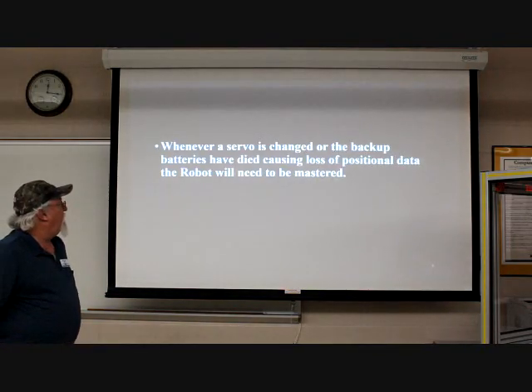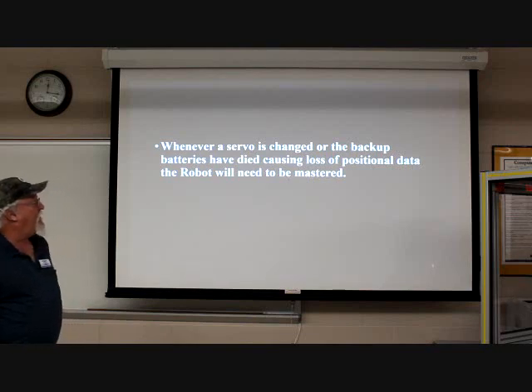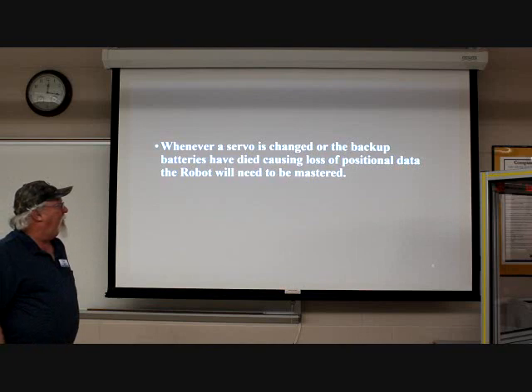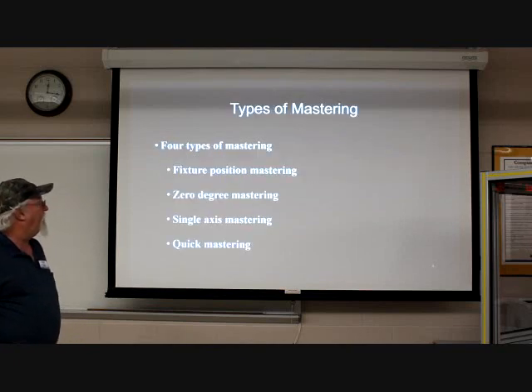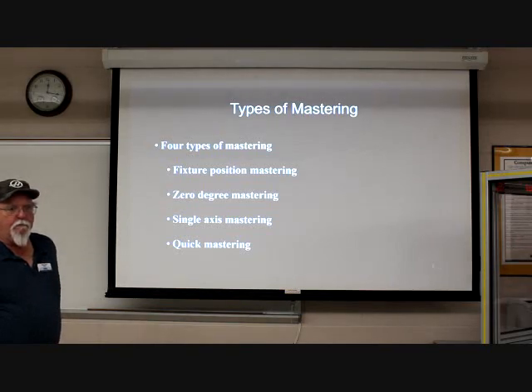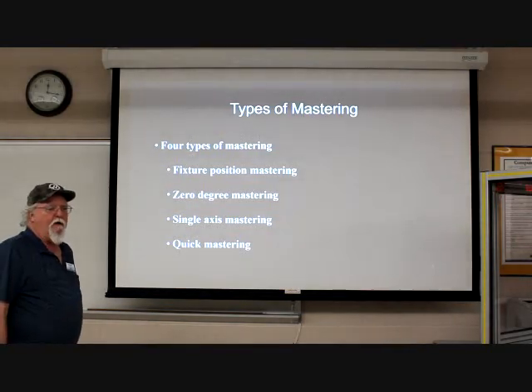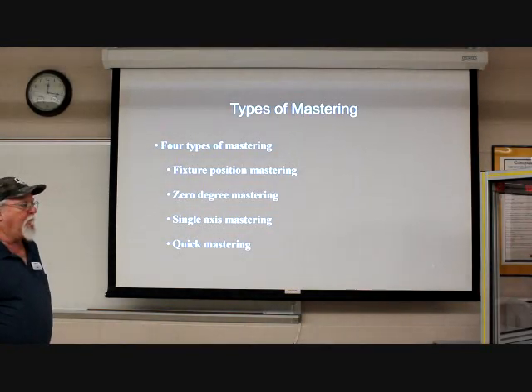When the servo is changed or the backup batteries have died, causing loss of positional data, the robot will need to be mastered. We can come across this when we're changing a servo. We've lost power in the batteries. We're not able to maintain the firmware in the controller.